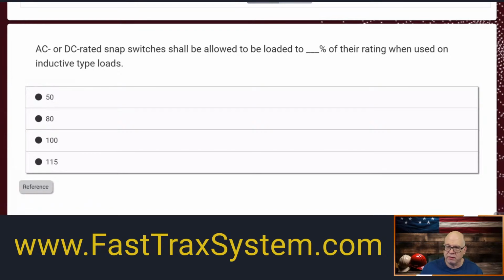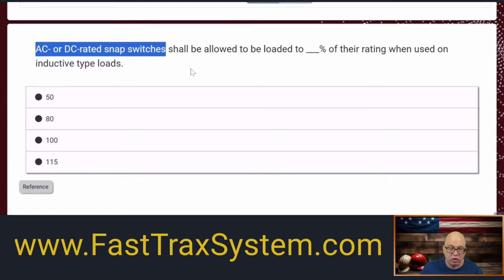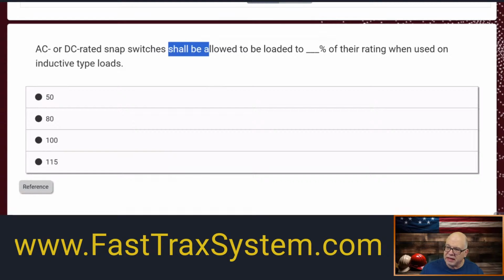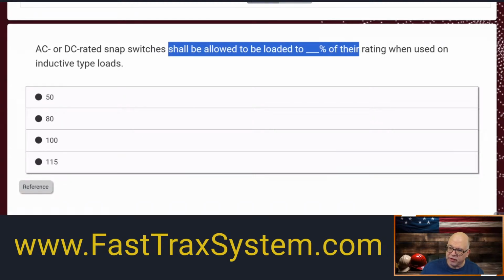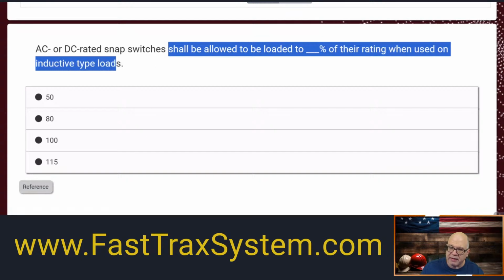All right, another question here. AC or DC rated snap switches, UL 20 by the way, snap switches, shall be allowed to be loaded to blank % of their rating when used on inductive type loads. So if I'm using an AC or DC rated snap switch, maybe using it as a disconnect or something of that nature, I have a rating that the switch is rated for, stamped on it. Okay, it's the manufacturer's rating. And here it's saying if I'm using an AC or DC rated snap switch, I'm allowed to what? It shall be allowed to be loaded, that snap switch, to what percentage of its rating when used on specific inductive type loading? Okay? So what is it?